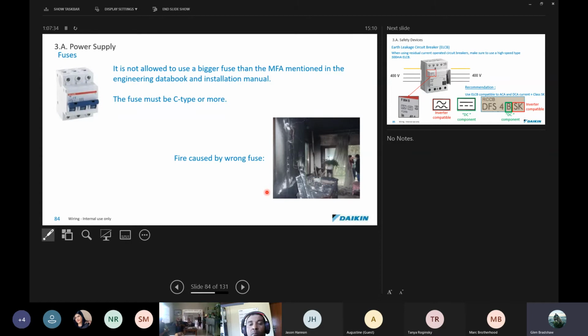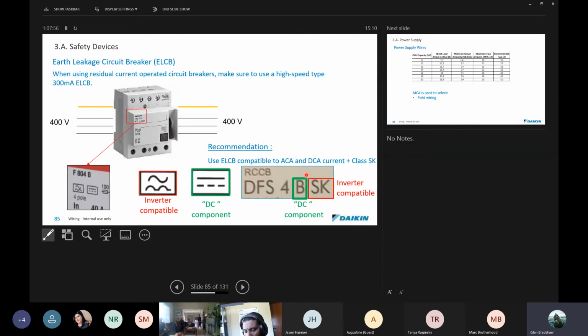It's not allowed to use a bigger fuse than the MFA mentioned in the engineering data book, in the installation manual, and the fuse must be a C-type or slow curve breaker. Using the wrong type fuse can create a fire risk. So don't use oversized fuses. Something we don't see much of in this country is earth leakage breakers, but if you're asked to use an earth leakage breaker, it must be inverter compatible, and the DC component as well, direct current component, and those symbols are what you should be seeing on there. This is a model number for a device that's not available here, so don't worry about that.